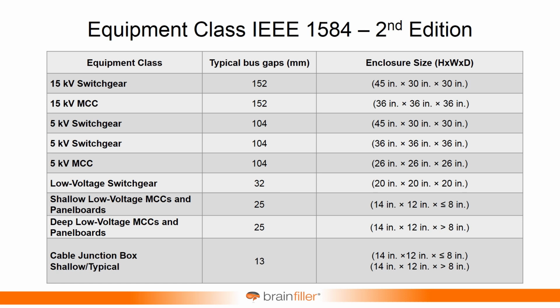And so starting at the top, we have 15 kV switchgear. We're still using the 152 millimeter gap, same thing that we had before. And we have an enclosure of 45 by 30 by 30. And then we have 15 kV motor control center, 152 millimeter gap, but the size is smaller for motor control center. And then we have 5 kV switchgear of a larger enclosure size, and then 5 kV with a smaller enclosure size. 5 kV motor control center, low voltage switchgear.